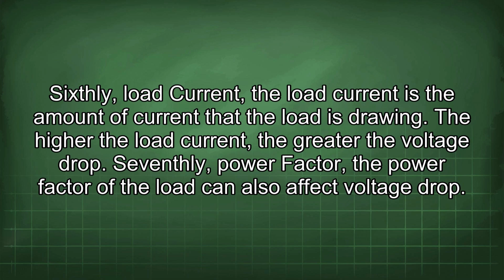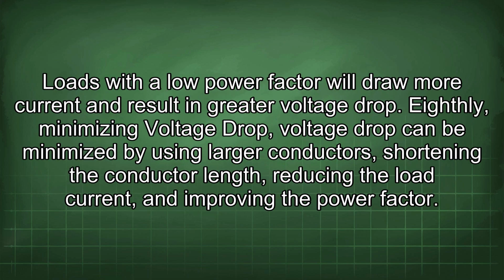Seventhly, power factor. The power factor of the load can also affect voltage drop. Loads with a low power factor will draw more current and result in greater voltage drop. Eighthly, minimizing voltage drop. Voltage drop can be minimized by using larger conductors, shortening the conductor length, reducing the load current, and improving the power factor.